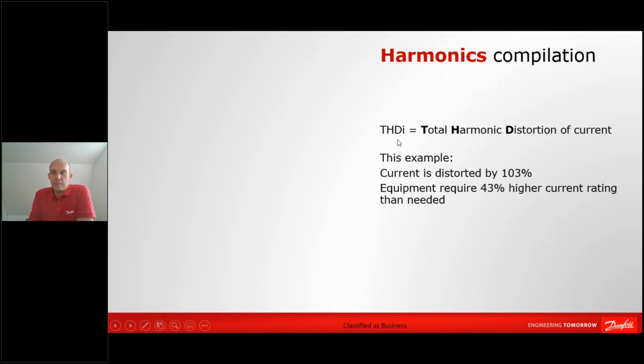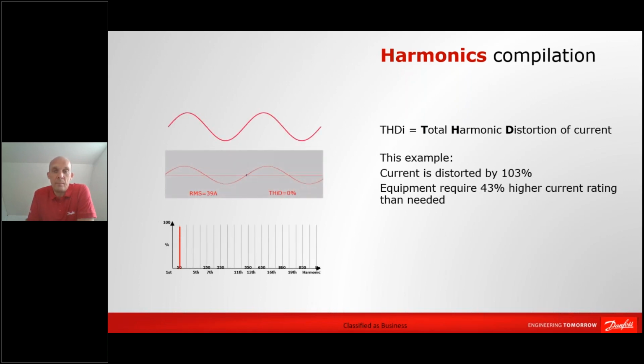First of all, if we look at the normal way of describing harmonics, it's done by an abbreviation called the THDI value, the total harmonic distortion of the current. You can also talk about the total harmonic distortion on the voltage, and then it's just THDV. But it's basically the same thing. This expression here tells you how far away the signal is from the ideal sinusoidal waveform. So if we take, for instance, the example you had before, the green curve from a frequency converter, and you want to see how distorted that is, then you need to do some math on it.